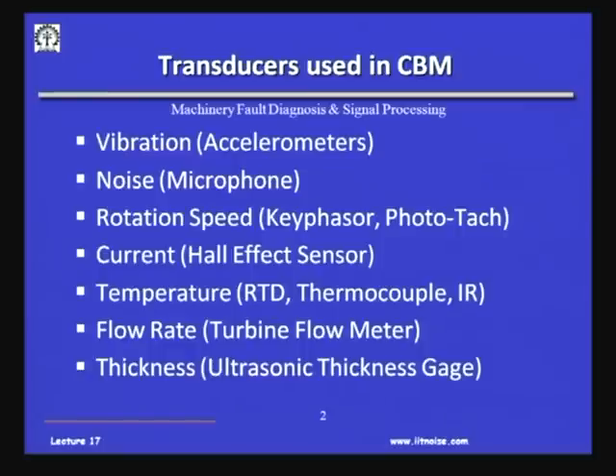A turbine flow meter is another device which can be very easily put online on a pipeline - all you will get is the speed at which the fluid is flowing through it. Once you know the area of the pipeline and multiply that, you get the flow rate instantaneously. When processes are very dynamic and flow rates are changing - particularly in large oil refineries and chemical plants - that is where we use turbine flow meters.